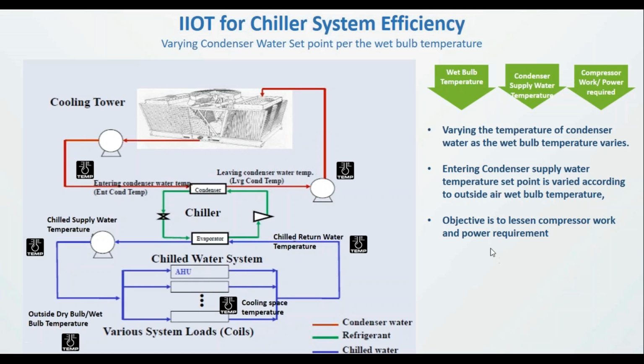There is a limit to this recommendation. Typically if the wet bulb temperature is below 75 degrees Fahrenheit, you may not end up saving a lot of energy, because you'll start consuming more on the motor side of the cooling tower. So all those rules and logic can be established in the platform so that we have the correct and appropriate energy recommendation and the appropriate control happening in the system.